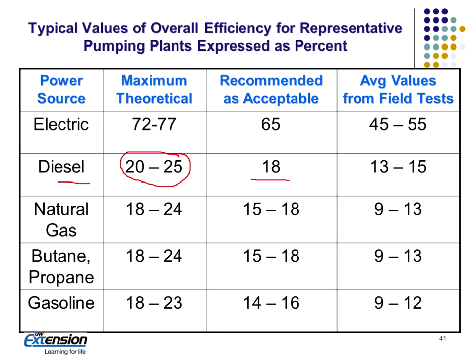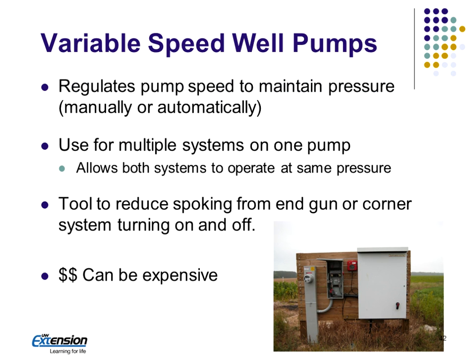Here's what the recommendation is. If you test one and this is what it runs into, 18%, then you probably leave it. But you can get lower values, and these are the average of what we come up with from field tests. So there always seems to be room for improvement. Most of the time, it's whether it's economical: are we going to save enough energy to pay for the cost of modifying the pump?